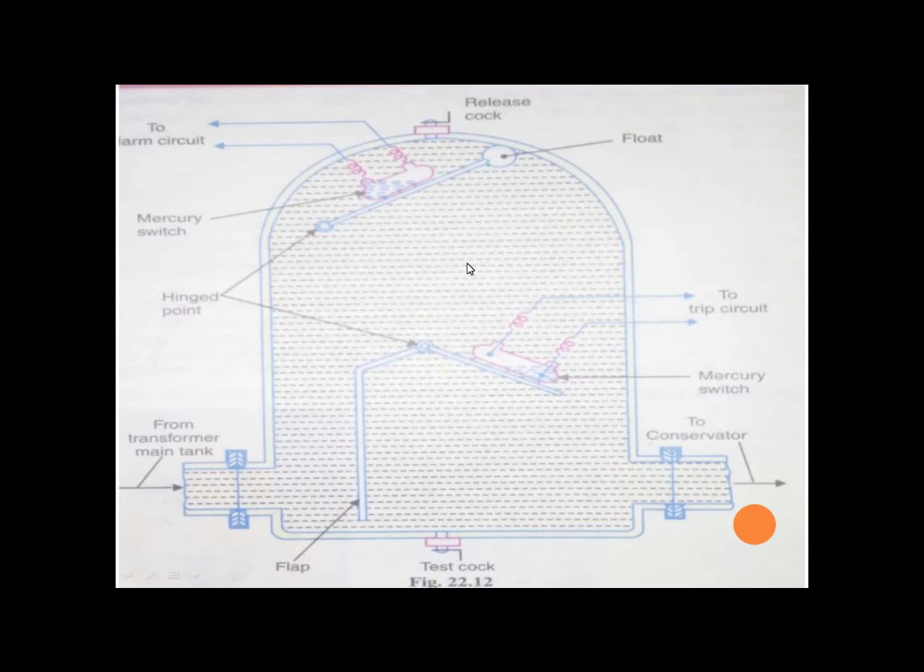Gases are produced, 70% of which are mostly hydrogen. As you start to produce gases, they go to the conservator side. But due to this flap wall, which is used to prevent the flow, the gases accumulate.